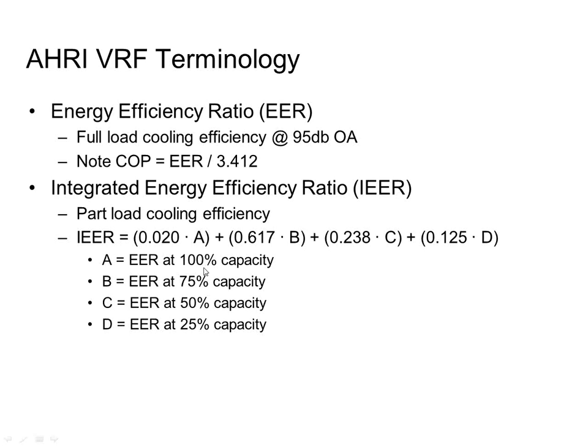And 100%, 95 degrees out, we're going to assume happens 2% of the time, which is almost nothing. So it's heavily weighted for the 75 and even 50% range. That middle range gets heavily weighted because that's probably where you're going to spend a lot of your runtime. So that's how you get these IEER numbers.